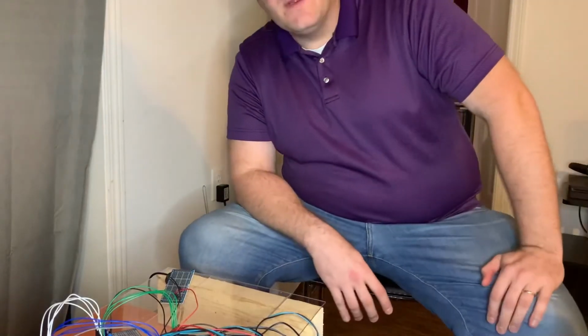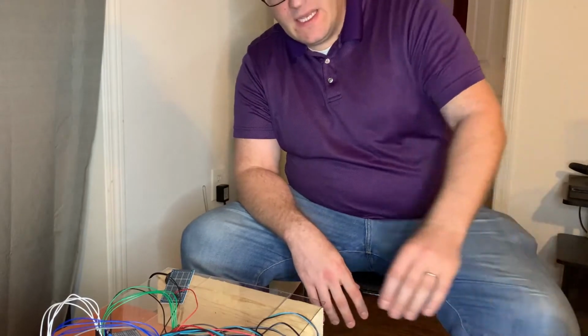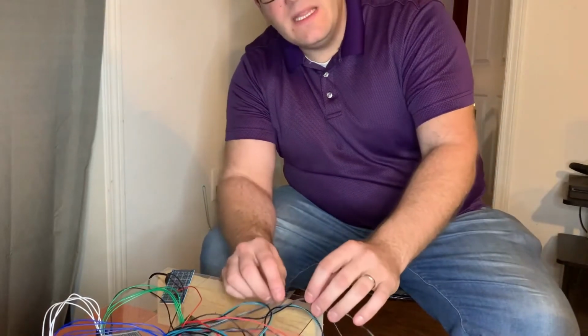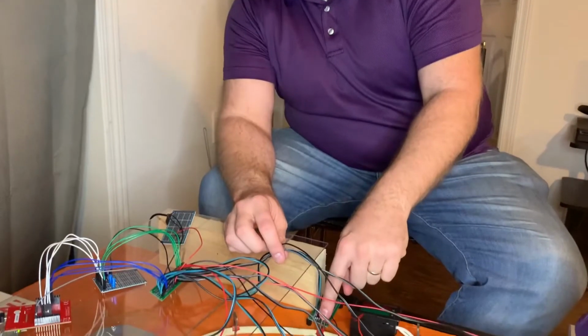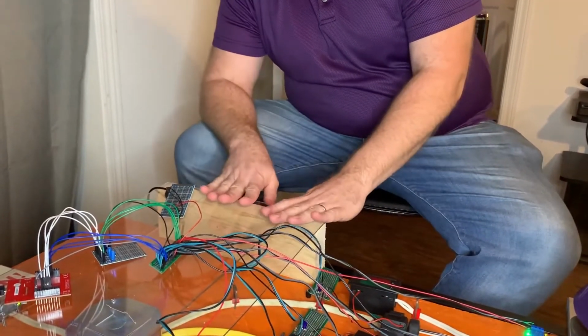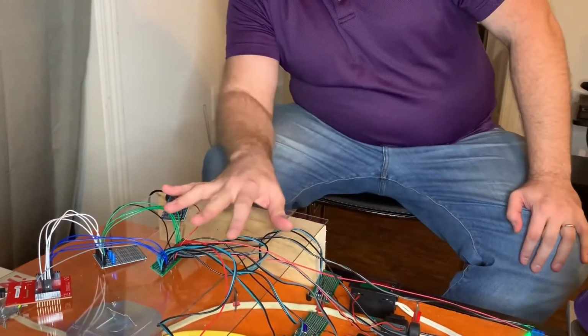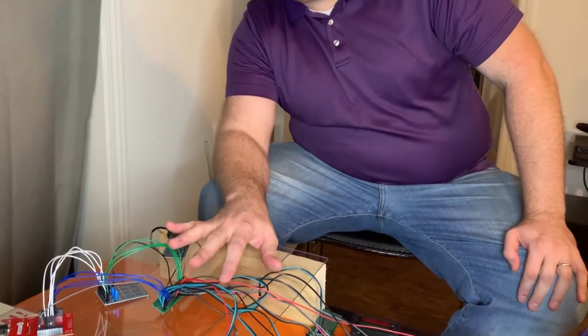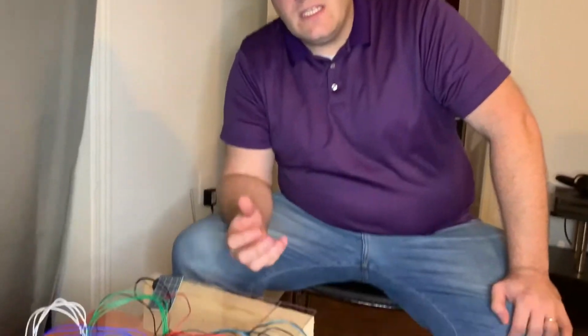In our project, we realized there was magnetic interference, specifically between these low voltage wires and these higher voltage wires. So we designed a plexiglass shield so that our low voltage wires could sit away from our high voltage wires. This reduced magnetic interference and allowed for higher accuracy in our current transformers that are reading the voltages on each line.